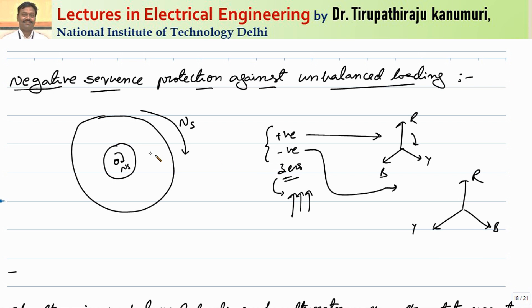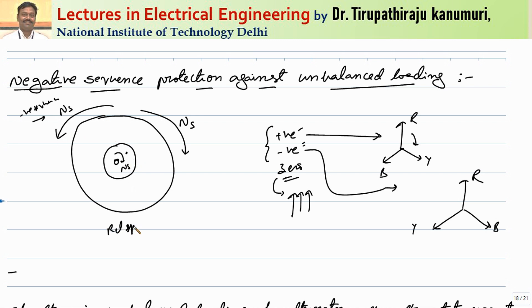Due to unbalanced loading — which is not associated with ground — both positive and negative sequence components will be present. The negative sequence component rotates at minus ns. The rotor rotates at plus ns, so the relative speed between the rotor and the negative sequence rotating magnetic field is equal to two times ns.